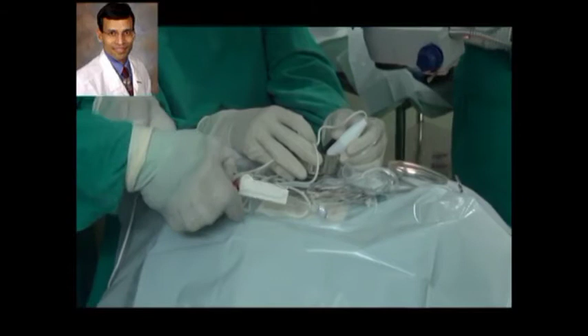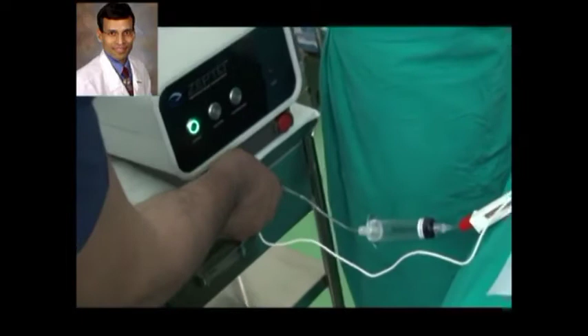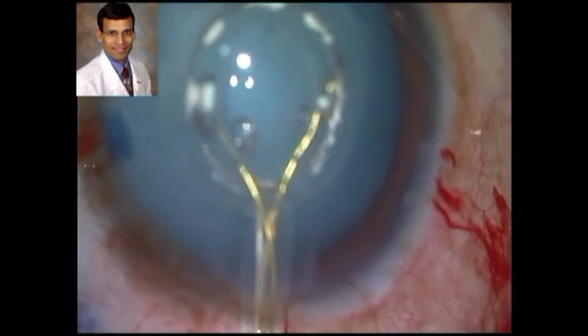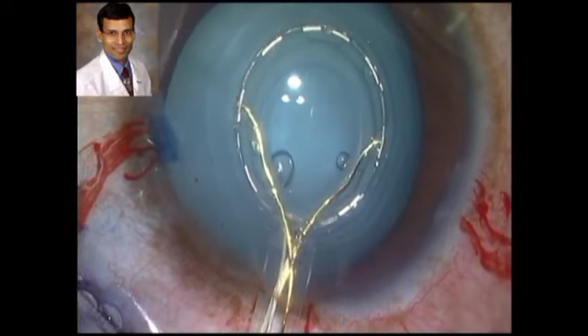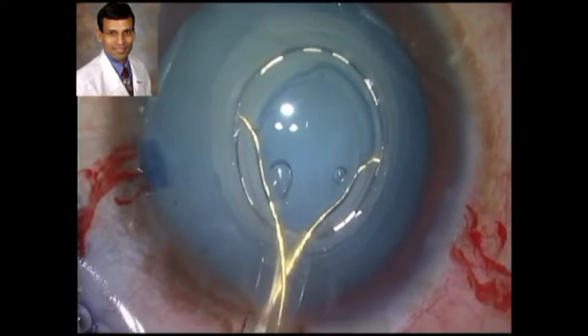Once the entire tubing is filled with BSS, we use this red button to lock the handpiece in a way, and after this we attach the tubing as well as the electrical wire to the console that comes with the machine. Once the surgeon is happy with the positioning of the device, he then asks the assistant to apply suction, for which a switch is pressed on the console. Once the suction is applied, the water molecules between the handpiece and the capsule are vaporized, and this creates the capsulotomy with the energy pulses that are delivered.